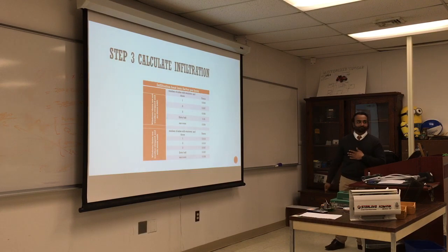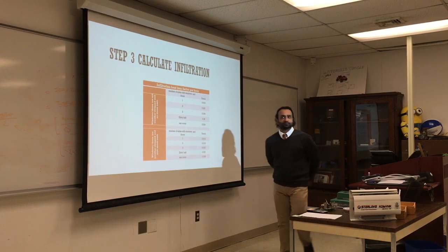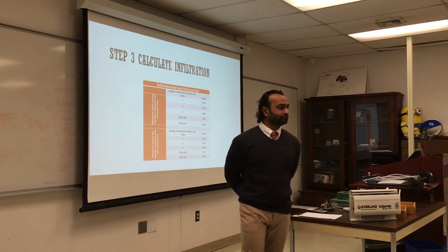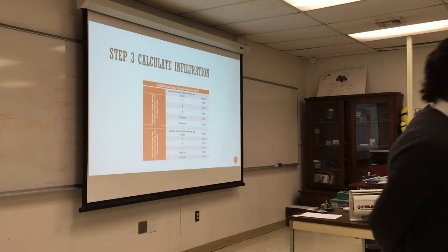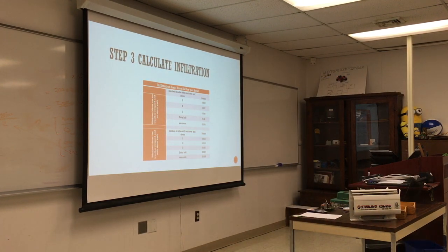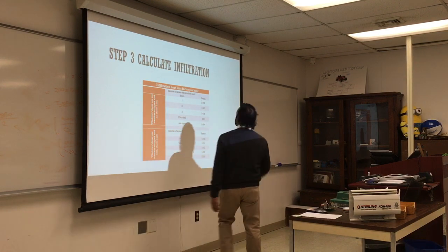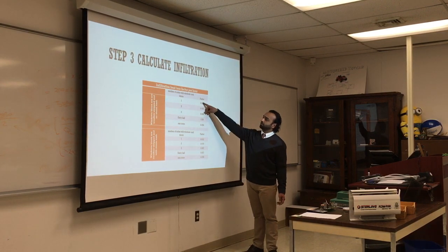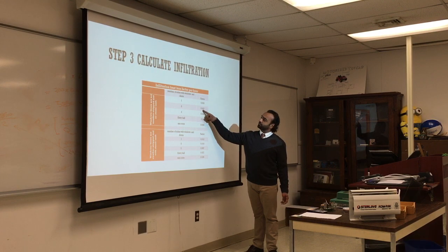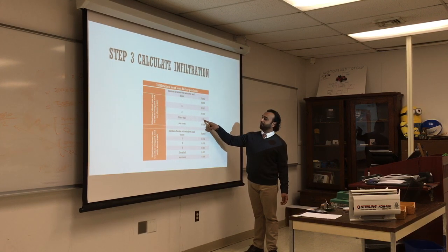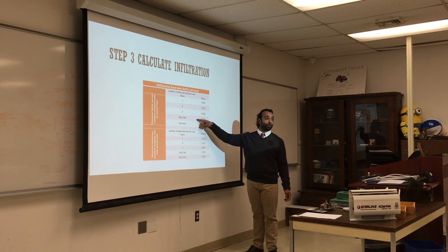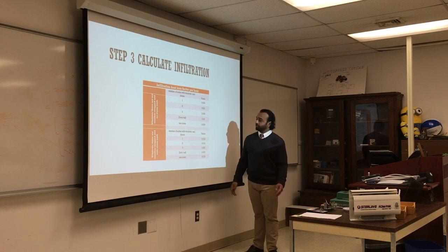Okay, if we were looking at this drawing, we would have to guess the size of the room. It's not giving dimensions, so we're going to have to do some measurement. The floor plan I'm giving you will have some dimensions in it. These are the factors, and I would say, actually, you're right, Chris, it's 0.036. One side, two sides, three sides. Entry hall is going to be 0.036, it's a lot, because we're opening the door and letting air in.